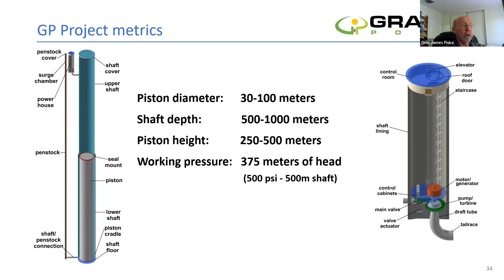In a very large gravity power plant, we can lift several million tons using totally conventional pressure from pumped hydro. At a 500-meter shaft depth, we're only getting 375 meters of head, which is right in the middle of pumped hydro ranges. With a 1,000-meter depth shaft, we get about double that, still in the range of conventional pumped hydro. But up to 5 or 6 million tons of weight can be lifted with this methodology.